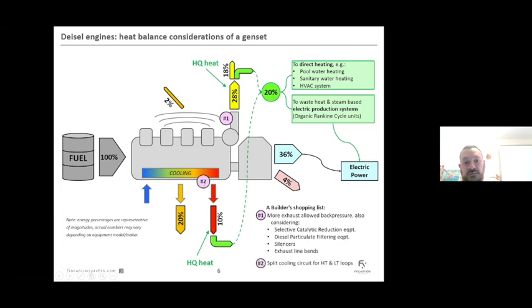The second item is split cooling loops for the high temperature and low temperature circuits, because only the high temperature loop is useful for heat recovery. Mixing it with the low temperature loop would impair this functionality.